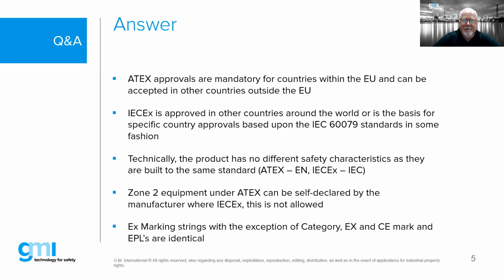So ATEX is mandatory within the European Union, but you do find ATEX showing up in other parts of the world, where people will say, I want ATEX, which is fine. IECEx is approved in other countries around the world, or is the basis for some of their own individual standards. So for example, if you go to Brazil, they have what are called the NBR standards, which are based upon the IEC standards. So getting Brazilian approval, if you have an IECEx test report, is basically a money issue, if you will.